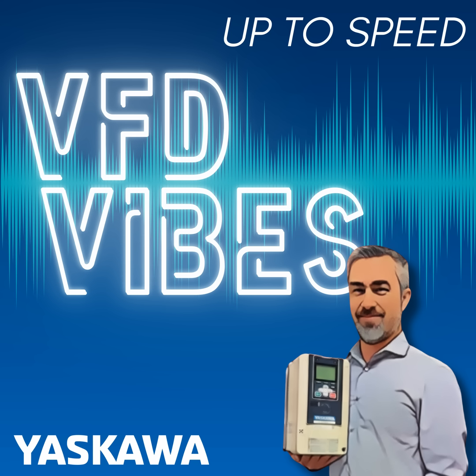A rare exception to this is Yaskawa's matrix drive, which actually does have input fuses embedded within the drive. That's a rare exception. Most drives don't include that. And for those of you that don't know, our matrix drive is our low harmonic and full regenerative drive offering. It's kind of cool that when they designed that, they built fusing into it. I've seen another term, and I know we're throwing a lot of terms and acronyms out there. This time it's AIC. So can you explain the difference between SCCR, which is short circuit current rating, and AIC, which is amps interrupting capacity?